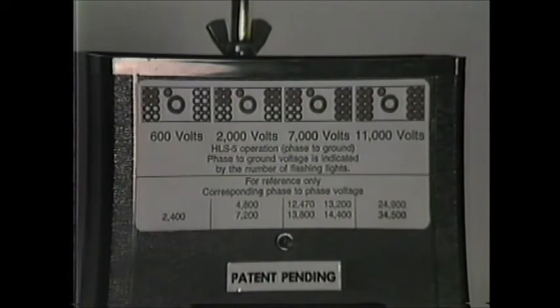Adapters are available to allow the HLS 5 to be used on 15 through 35 kV underground systems. These adapters allow the HLS 5 to be placed directly on the underground bushings. Due to the proximity of grounds on underground equipment, the HLS 5 will usually have one more bank of lights lit than would be expected when used in an overhead system. Because induced voltages are not as prevalent on underground systems, customers have not found this to be an operational problem.